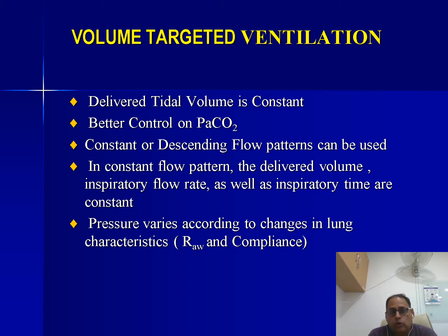You can set the flow patterns here. So it could be a constant flow of air, or a descending flow pattern starting from higher can be used. Remember, in pressure ventilation only descending flow is available. So in constant flow pattern, the delivered volume, the inspiratory flow rate as well as inspiratory time remain constant. So what varies in volume ventilation? Obviously the pressure varies. And how does it vary? It varies as per the airway resistance and the compliance of the lungs.